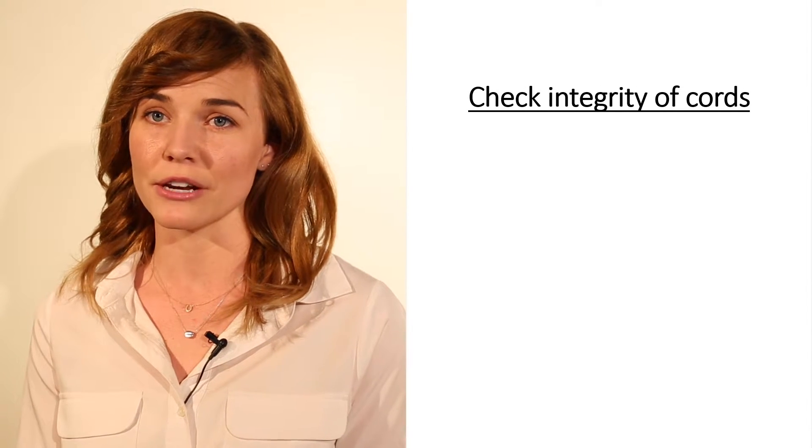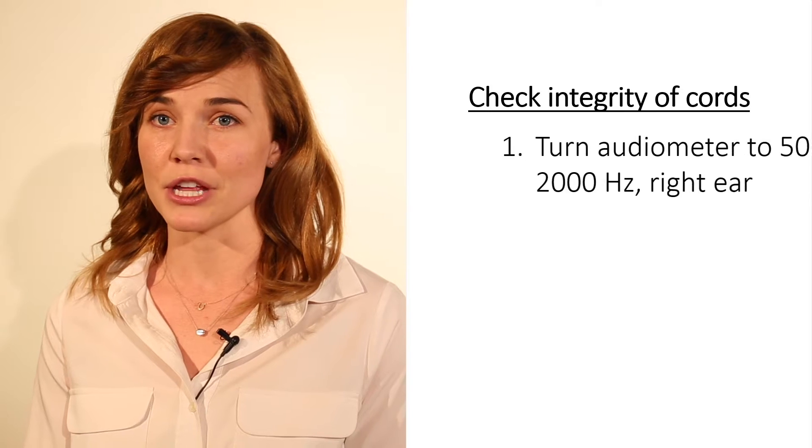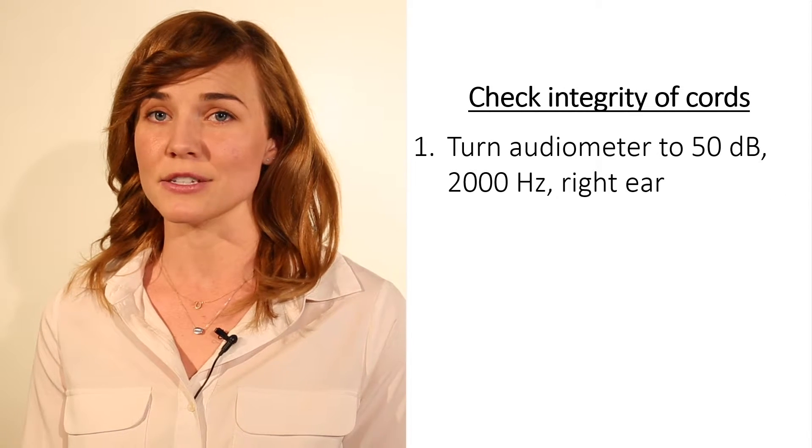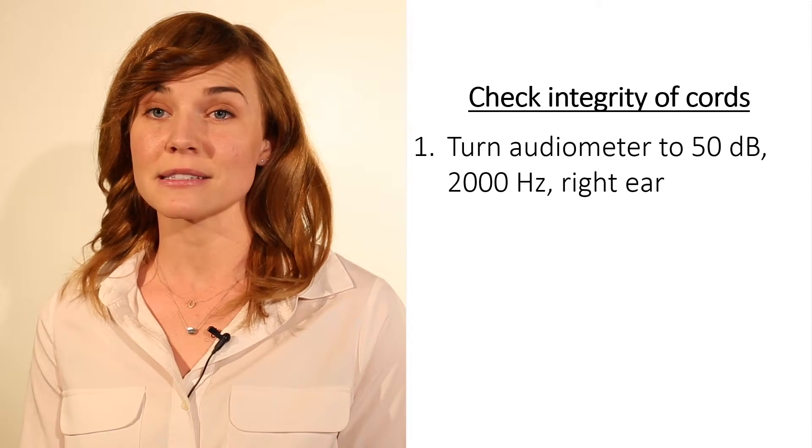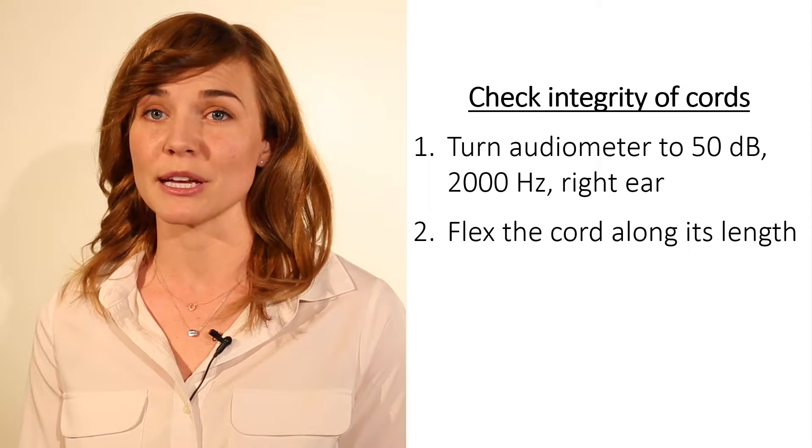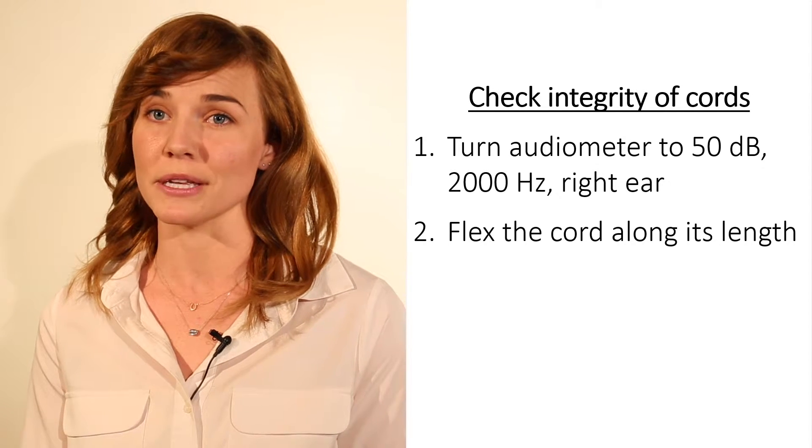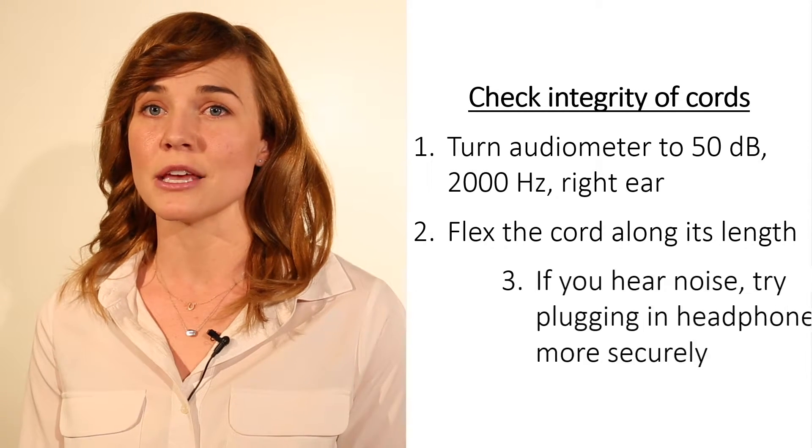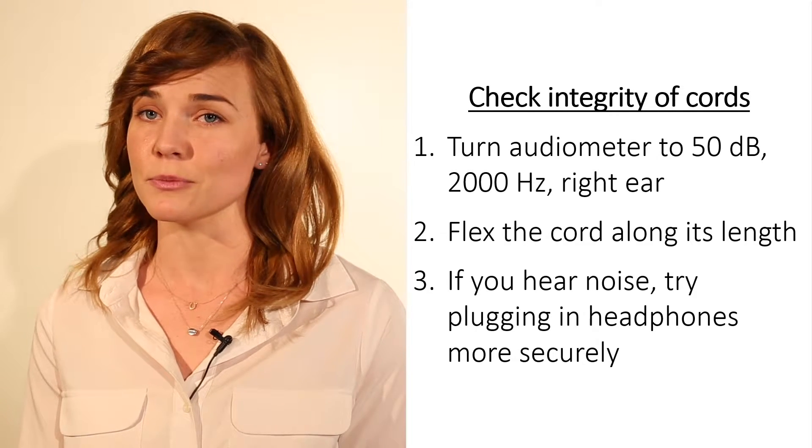Sometimes old cords can create scratching or interrupted sounds. Test for this by turning the machine to 50 dB and 2000 Hz. Flex the cord along its length, paying special attention to its connection points. If you hear noises, you may just have to plug in the headphones more securely.